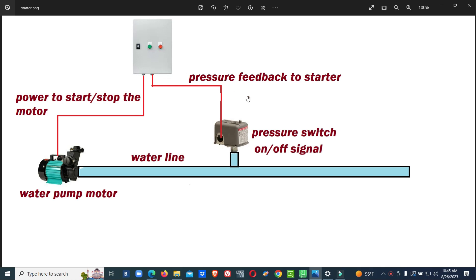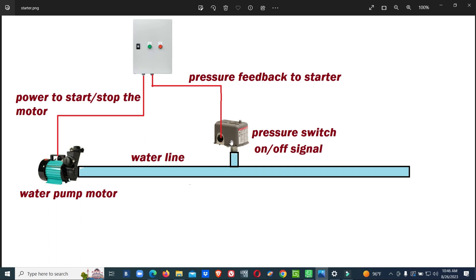This is a normal pressure maintaining system. You can see one water pump feeding water to the water line, and a process is connected to the water line. The pressure switch senses the pressure level and gives a signal to the starter panel. The starter panel cuts in or cuts off power to the pump to maintain a certain pressure. Based on the setting of the pressure switch, it will turn on/off and give the control signal to the starter to power up or power down the motor supply.